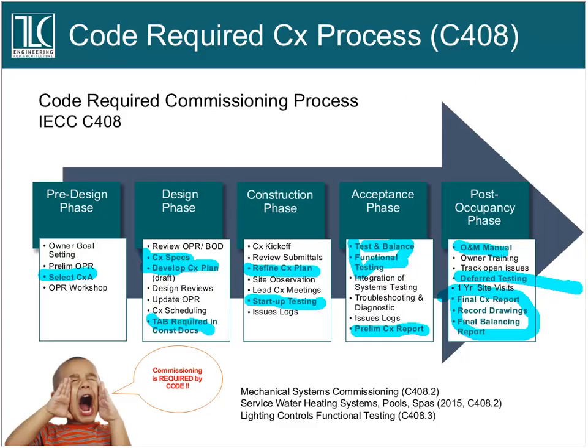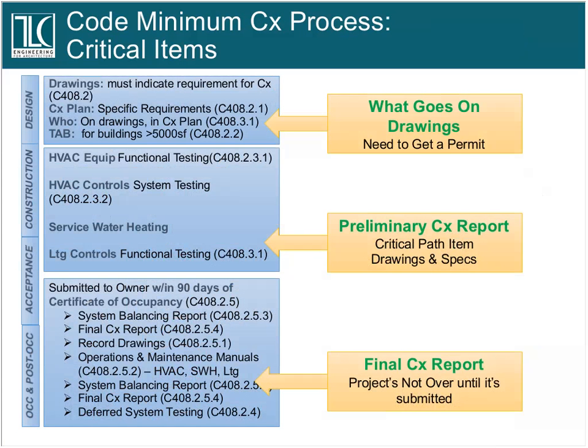On mechanical systems, it's if your building system has 40 tons of air conditioning or more. For service water and lighting controls, it's all buildings. Must be commissioned. You've got to put the requirements for commissioning in the set that goes to get a permit. So no more waiting till the project is almost complete in construction to do commissioning. The commissioning plan, who does the commissioning, what's going to be commissioned, how it's going to be commissioned, needs to be in place to get a permit. You must complete the mechanical commissioning to at least a preliminary status, identifying any critical path items, before acceptance. There will be no mechanical final inspection done until the owner receives the preliminary commissioning report.